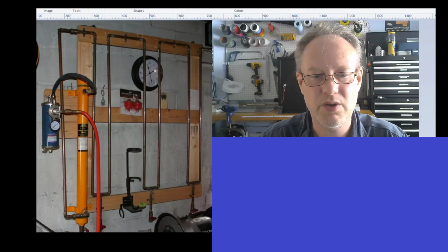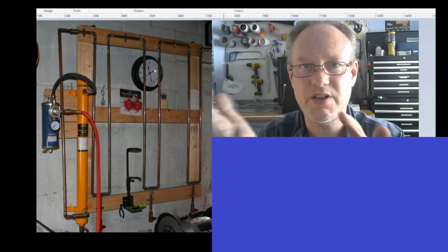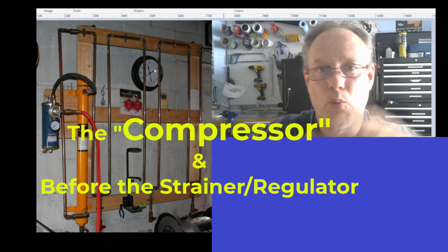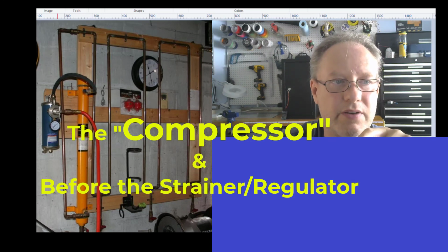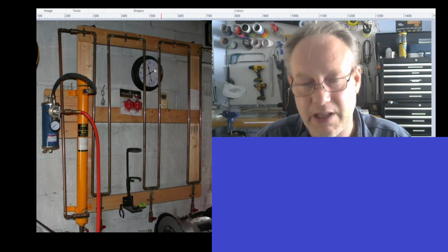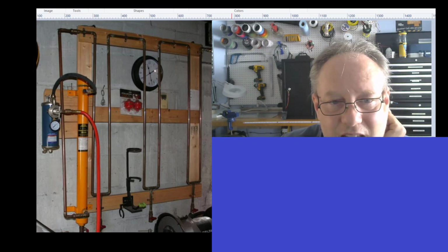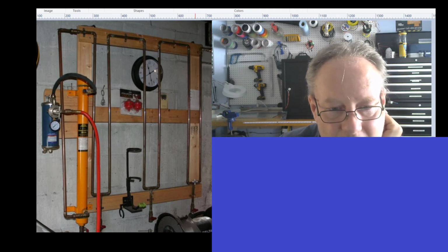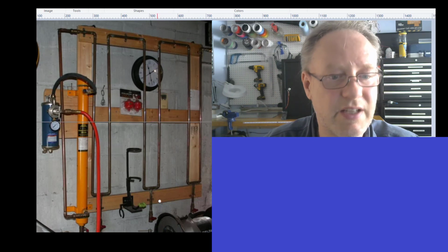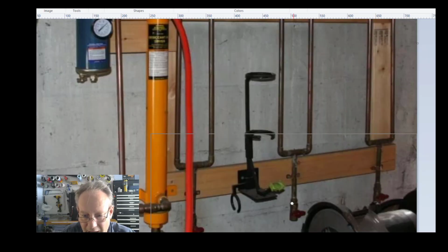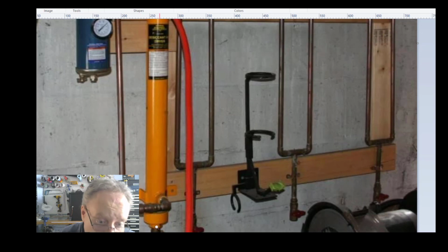Now, somebody went to some really serious business to get some water out. Let's take a look at this. Remember how I told you we put our air filters after the water separator? Somebody made some kind of system here that is removing a lot of water from the system. It's kind of MacGyvered or makeshift, but that's okay. It's working. The air is coming in from over here, goes down here, and there's a drain in here, a drain here, a drain here, and a drain at the bottom of the moisture separator as well.